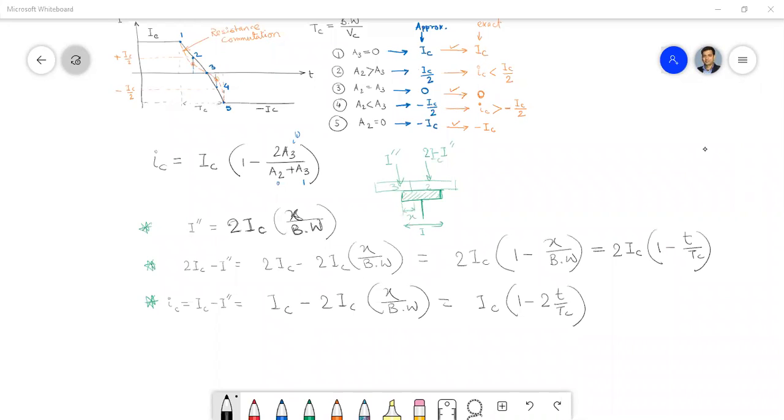Doipayan Guho. Yes, sir. Can you explain? So the total current from the two segments is always 2 IC. Right now we are assuming that the area of the brush in contact with the third commutator segment is X. So the ratio of the current coming from that commutator segment will be X by the brush width. So that's why 2IC into X by the brush width.